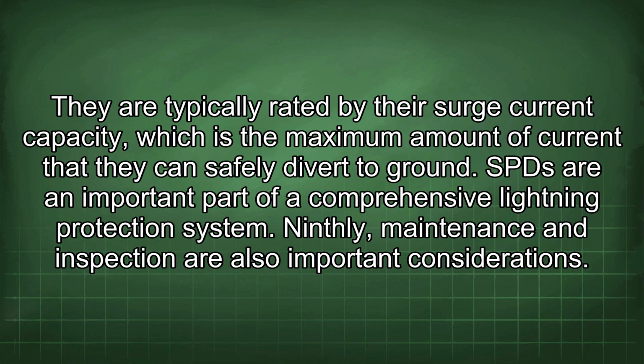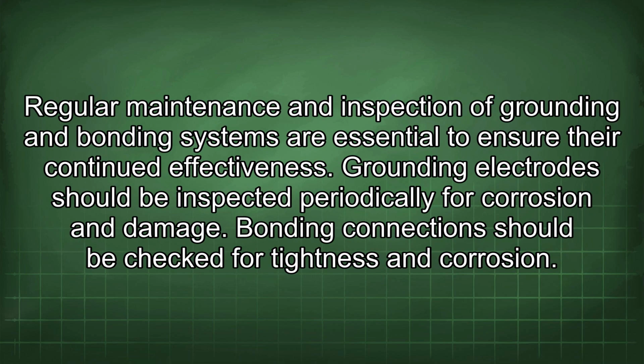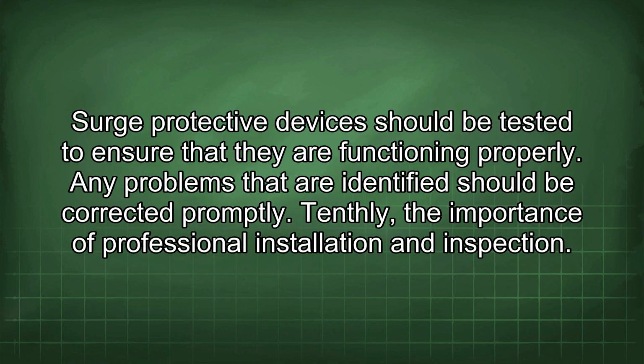Ninthly, maintenance and inspection are also important considerations. Regular maintenance and inspection of grounding and bonding systems are essential to ensure their continued effectiveness. Grounding electrodes should be inspected periodically for corrosion and damage. Bonding connections should be checked for tightness and corrosion. Surge protective devices should be tested to ensure that they are functioning properly. Any problems that are identified should be corrected promptly.